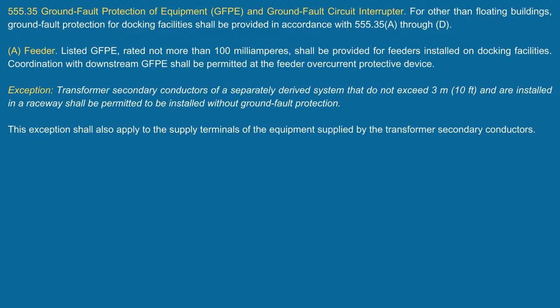Now, we have to be careful with the word outlet in this section, because it doesn't say receptacle outlets, it doesn't say lighting outlets, it just says outlet. Remember that an outlet, as defined in Article 100, is a point on the premises wiring system where current is taken to supply utilization equipment.